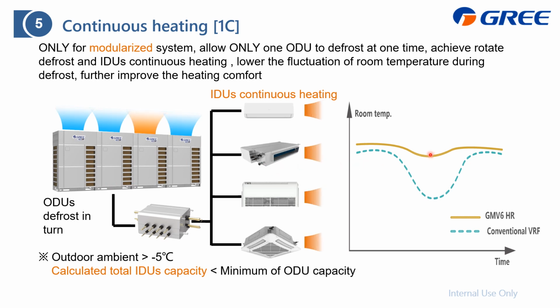And here is the comparison between this new and the conventional methods, which is for this conventional, during the defrost, the indoor unit stops, which also leads to the room temperature dropping much. But for the new method, you can find that the indoor room temperature just drops a little bit. For this, we can further improve the heating comfort.